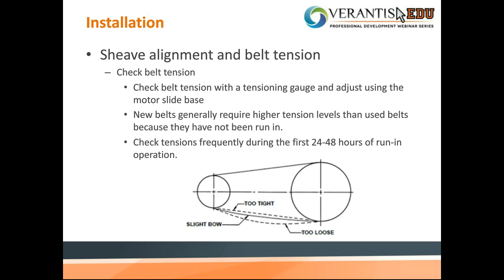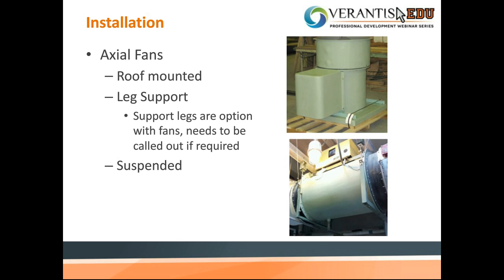So there's a slightly different installation for axial style fans. Basically, there's rooftop versions, leg supported versions, and suspended. They're a little bit trickier, but you still want to have the same principles, where, especially for an inline style fan, you don't want it to be coupled directly to the ductwork. You want it to be on its own separate system. That's why we use flex connectors on the inlet and outlet. Typically those are flanged flex connectors. On top of that, you can also do vibration isolation through spring hangers to make sure it's an independent system.